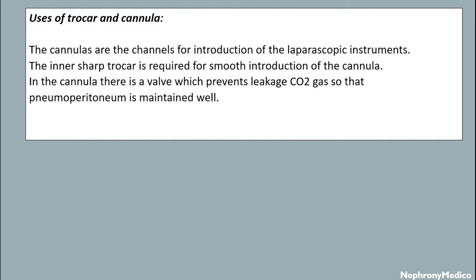Functions of trocar and cannula. The cannulas are the channel for introduction of laparoscopic instruments. The inner sharp trocar is required for smooth introduction of the cannula. In the cannula, there is a valve which prevents leakage of carbon dioxide gas so that pneumoperitoneum is maintained well.